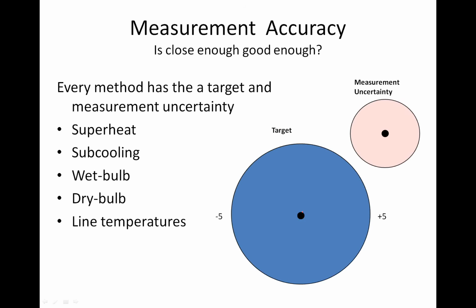And I don't care whether you're talking superheat, subcooling, a wet bulb temperature, dry bulb temperature, a line temperature, any measurement you make, you got to look at the accuracy of the equipment you're using, and you got to look at the target. How accurate do you want to be? If you're going to be plus or minus a half a degree in temperature, you're going to require a very, very expensive thermometer to do that. You're not going to do it with a standard K-type bead probe thermocouple. That might be plus or minus 4 degrees, right? So that's a very inexpensive solution, but it gives you a very inaccurate measurement when you look at a measurement uncertainty of 1 degree. And that's why sometimes you got to spend a little bit more money on instrumentation when you're looking at what's the degree of uncertainty we're allowed to have.